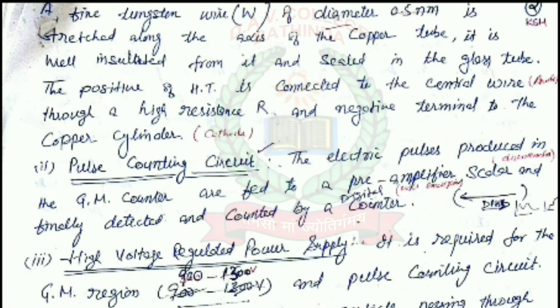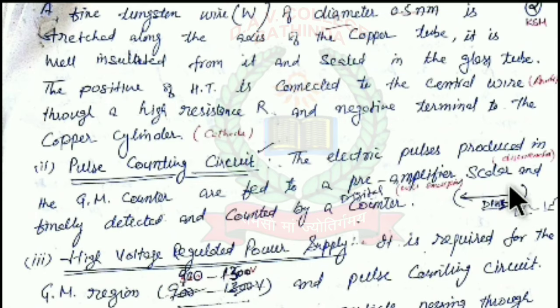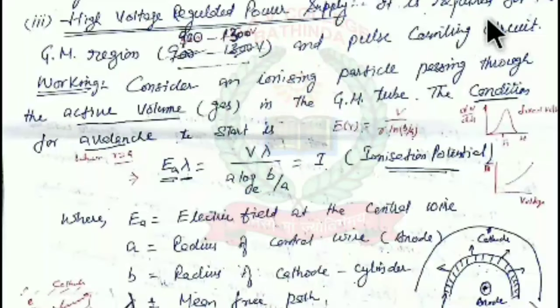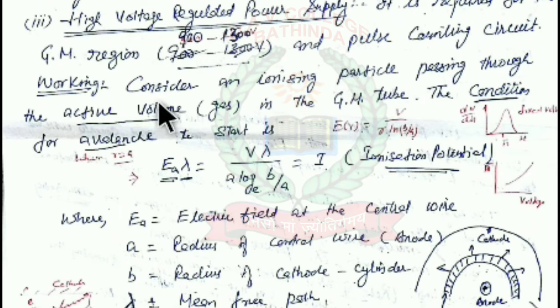The pulse counting circuit receives the electric pulses produced in the GM tube, which are fed to a pre-amplifier, then to a scaler, and finally detected and counted by the counter. The regulated high-voltage power supply is required for maintaining the GM operating region and powering the pulse counting circuit.